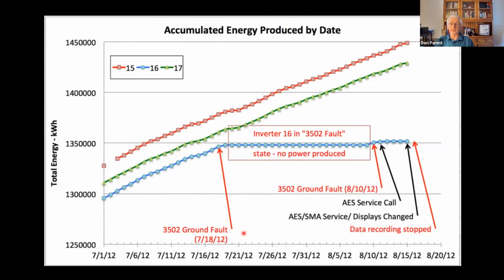But there's no evidence, no documentation of anybody going up on the roof, or any documentation as to what they saw in the inverter. But we do know this inverter was put back into operation, except that it didn't produce any power for almost a month's period of time. And the owner of the facility never noticed that there was no power being produced. The other thing that was noticed in the data is that every single one of these days resulted in maximizing the number of anomalous conditions reporting.